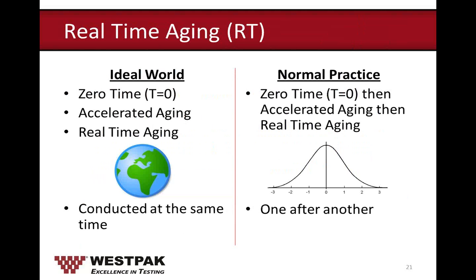According to ISO 11607, accelerated aging and real-time aging should begin at the same time. However, this isn't normal practice. In an ideal world, zero-time testing — conditioning and package performance — would start simultaneously with accelerated aging and real-time aging, using the same batch of samples. However, most customers don't do this. They ship zero-time samples for testing first to make sure they pass before spending time and money building more samples for aging.